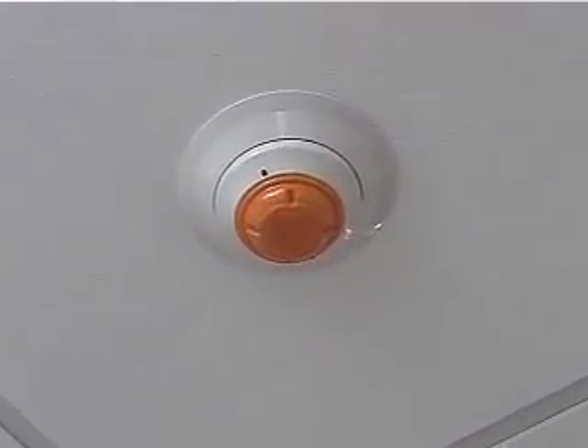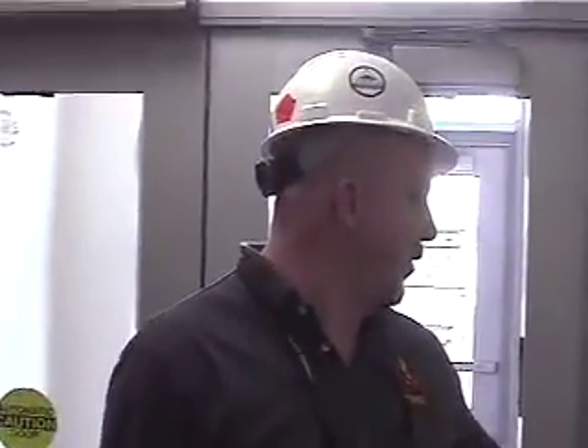Each of your detectors are labeled, and you can barely see it with the cap on, but it'll have N1 and then L1S00, I think that was 7. So it gives you your node and the loop and the device number. S is for sensor, M's for module, so any monitor point, pull stations, tamper switches, water flows, those will be an M. Your smoke detectors, duct detectors, any heat detectors, they'll be an S after the loop. So that just differentiates sensor from module.